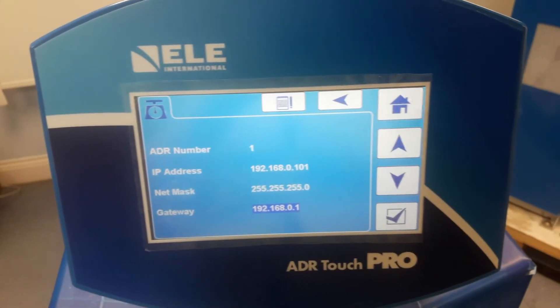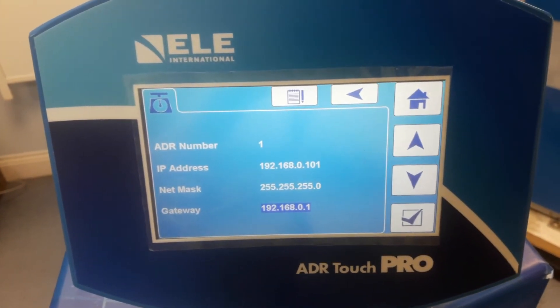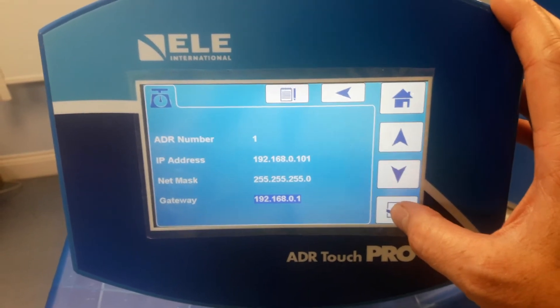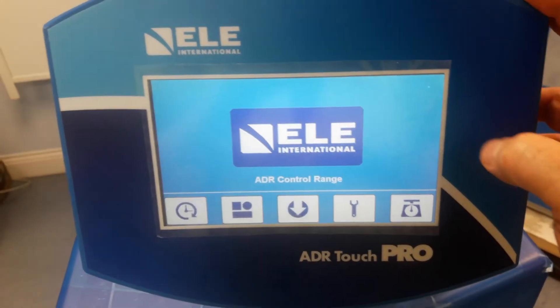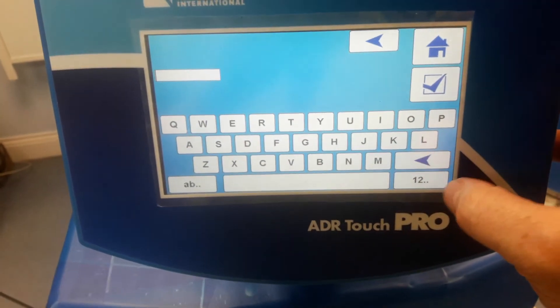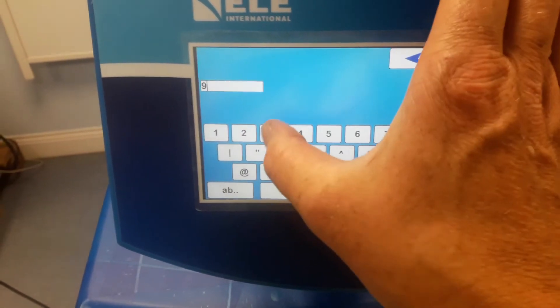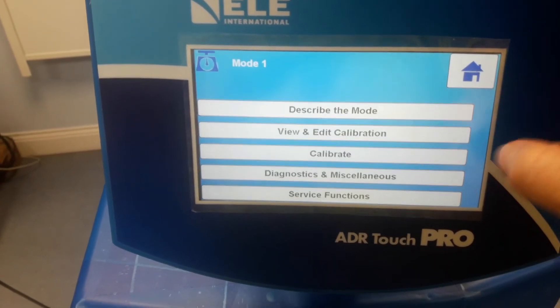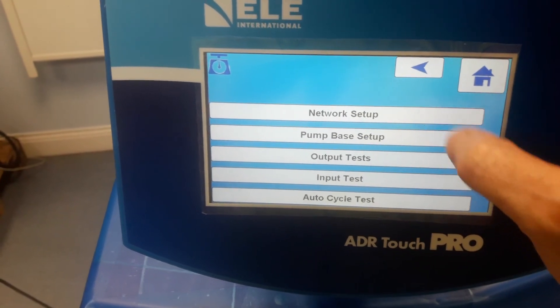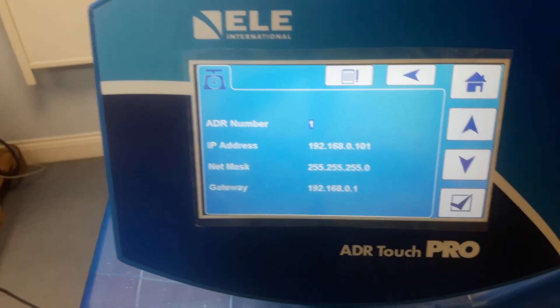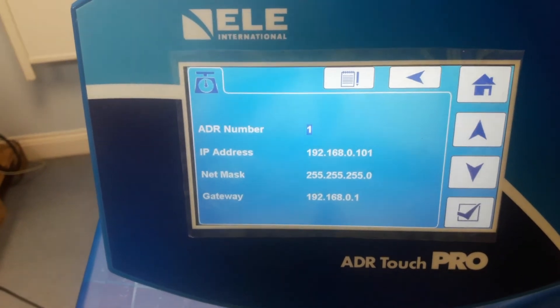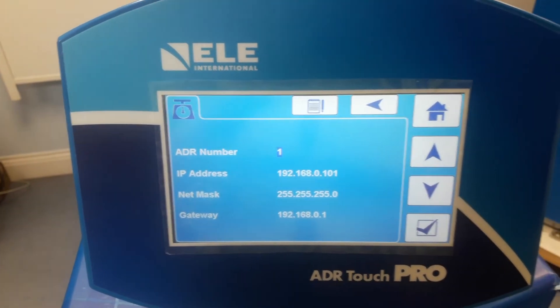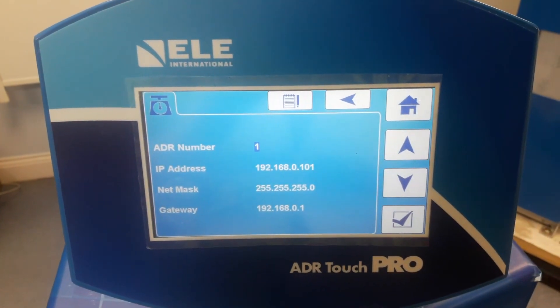As long as it matches the configuration of your PC, that's fine. Now we have these values in, we must make sure we press Enter and go back to the home screen. We re-enter the password protected area, press Enter, go to Diagnostics and Miscellaneous, then Network Setup — and you can see the values we set are now stored in the machine, ready to be used on a network.